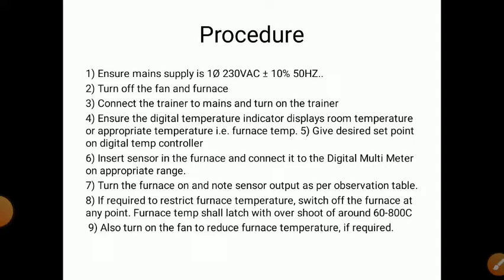At the end, turn on the fan to reduce the furnace temperature back to room temperature. In summary: put the sensor in the furnace, start the furnace, and take readings at every 10 degrees Celsius interval. After taking all readings, stop the furnace.